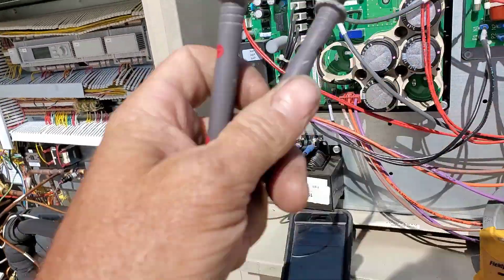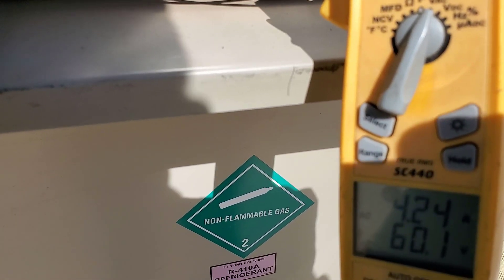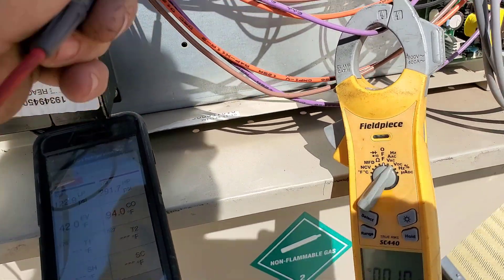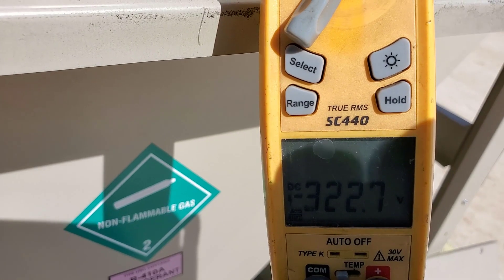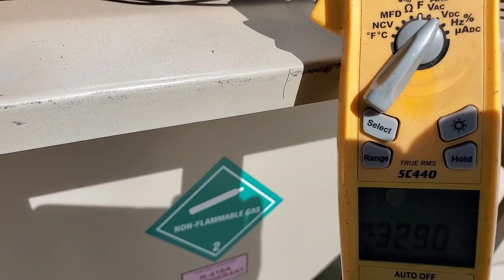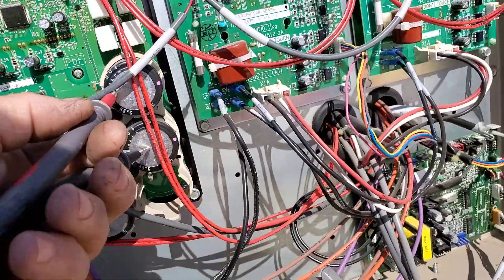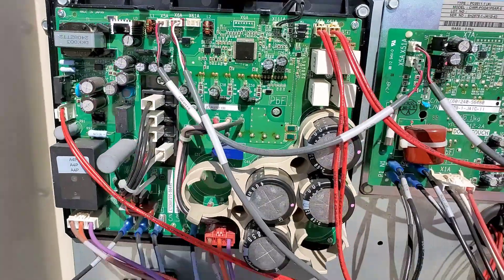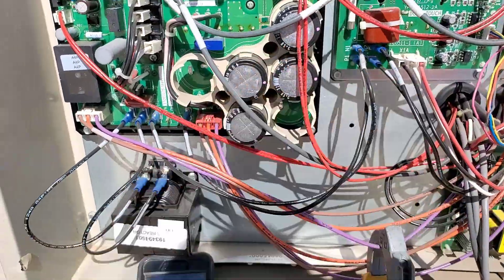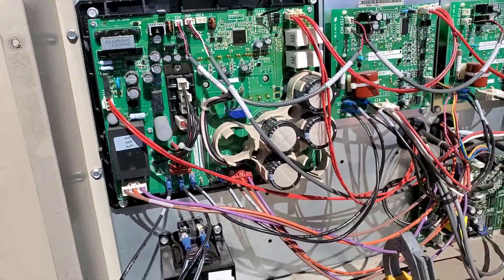Let's check voltage. Going to the top of the capacitor - it's reading about 767 volts. A lot of capacitors like this, the end plate has a potential. Going to DC power to ground just to see what you get: 320 volts to ground right there. That might shock the living daylights out of you. So you can get shocked if you ground yourself and touch the backs of those capacitors - keep that in mind. You learn from doing it once, twice, three times like I have.